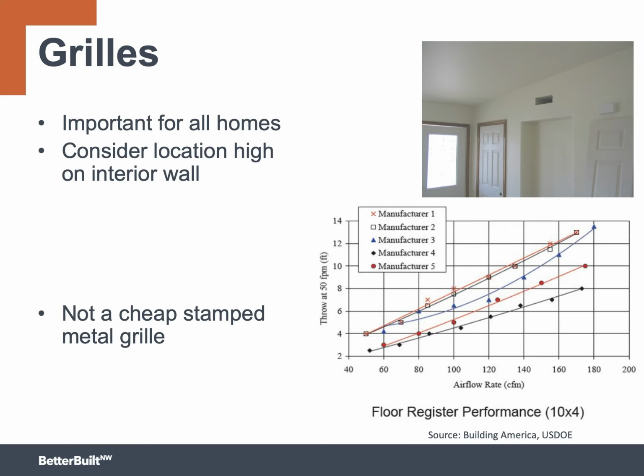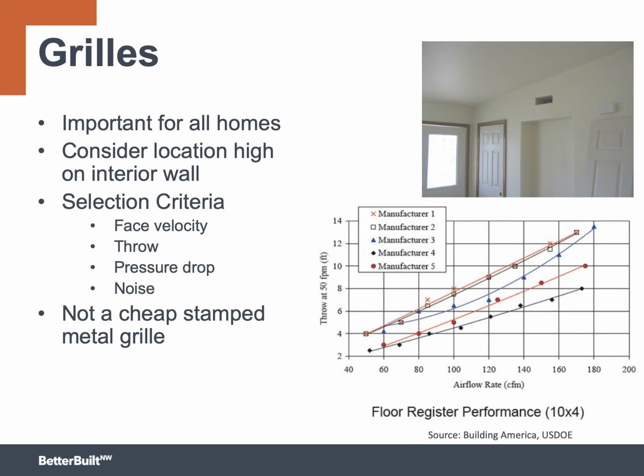Now, it's not to say that it can't work. You just have to think about this and make sure that you're going to get the proper throw and mixing of the air. The design guidelines for grills are included in ACCA Manual T, which stands for terminal, and that procedure can help you pick the proper grill. Then you can go to the manufacturer's information and select the product that meets your needs. In some cases, these grills are going to be more expensive, but again, it makes some sense to put thought into this and select the proper grill for your application.